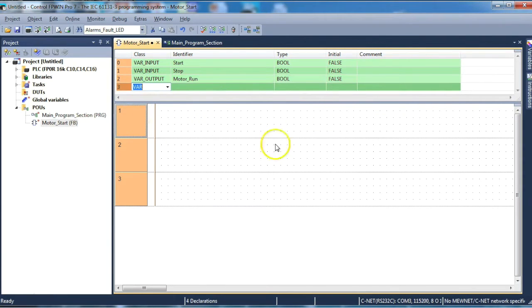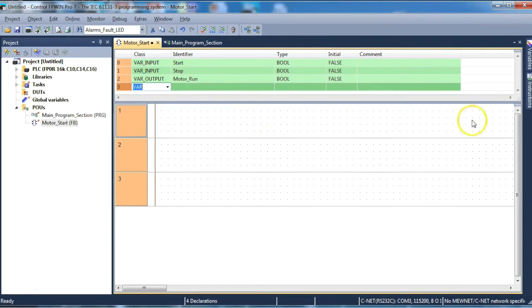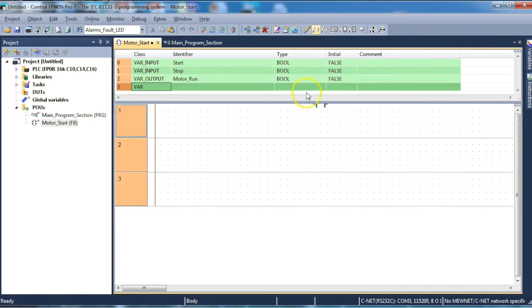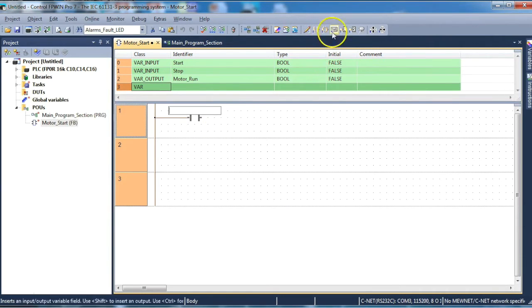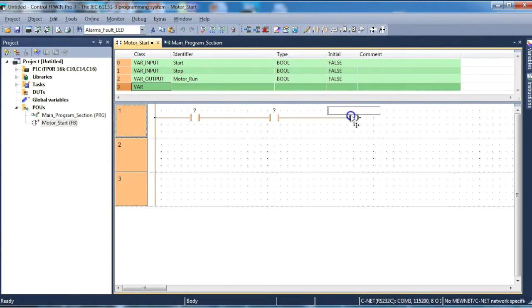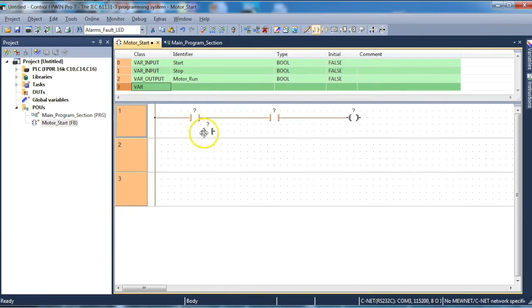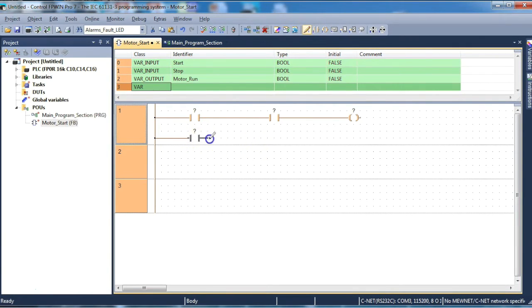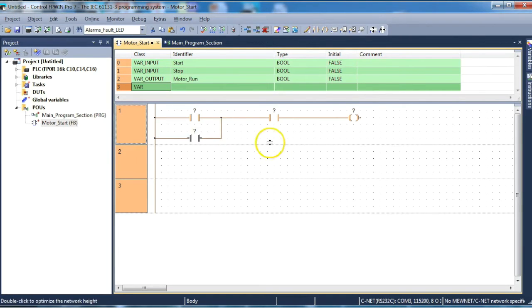So our next job now is to create the code that goes within the function block itself. What we do initially is click on the first section. We go up and we select a contact. Place our contact. Second contact. And a coil. And in this case we want to create a latch circuit. So we need one down below. Finish the code with the pencil tool. Right click to get rid of that. And now we have our basic code.